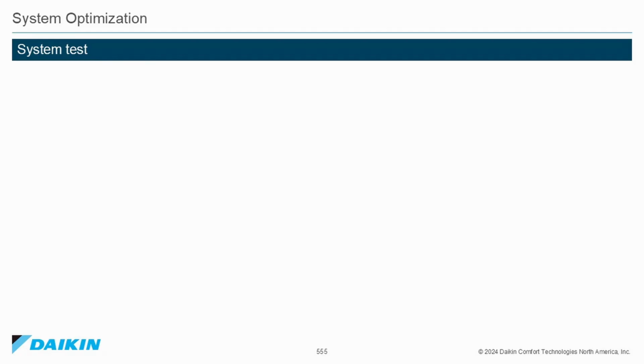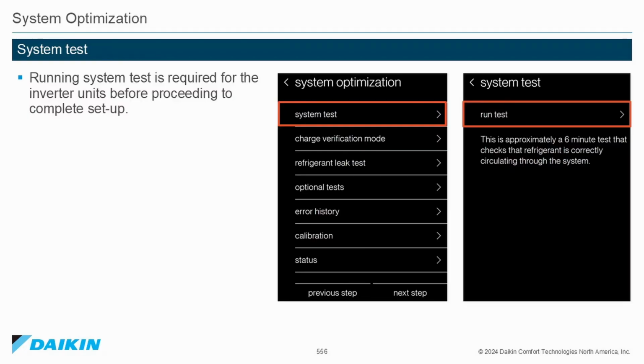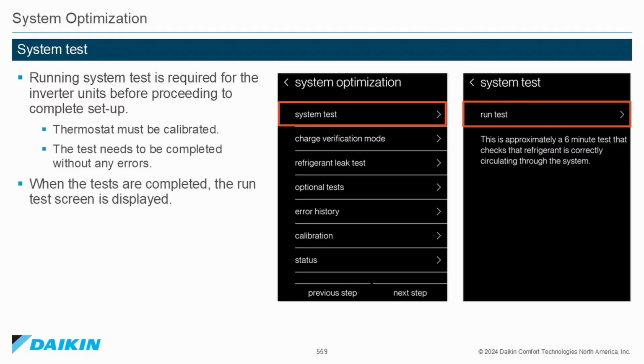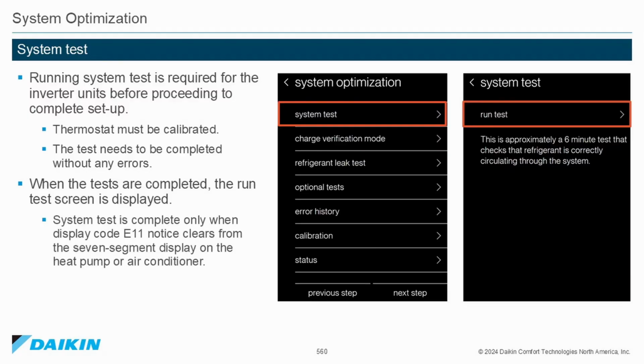System optimization. System test. Running a system test is required for the inverter units before proceeding to complete the setup. Thermostat must be calibrated. The test needs to be completed without any errors. When the tests are completed, the Run Test screen is displayed. System test is complete only when the display code E11 notice clears from the 7-segment display on the heat pump or air conditioner control module. System must be in off mode while running the tests for the E11 code to clear.